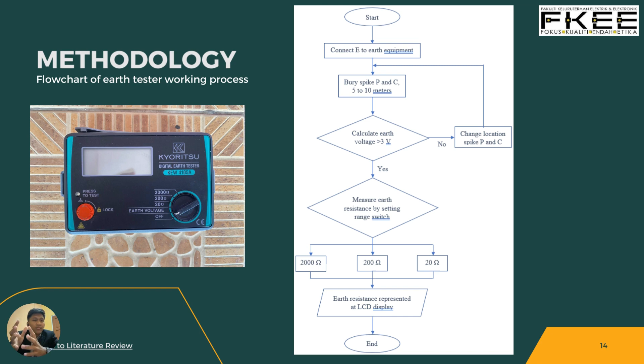Then we calculate the earth voltage. If it is less than 3 volts, we measure the resistance directly by setting the range switch. But if it is more than 3 volts, we need to change the location of spikes P and C. After measuring, we set the range: first 2000 ohm, second 200 ohm, and third 20 ohm. Then the result is shown on the LCD display.